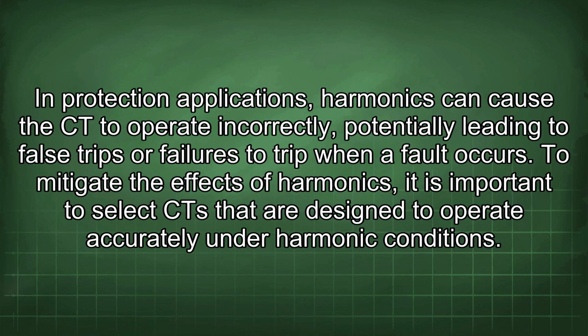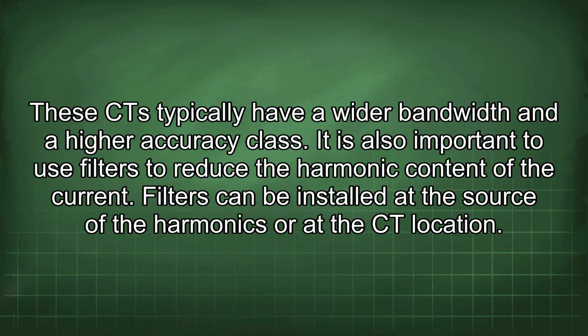In protection applications, harmonics can cause the CT to operate incorrectly, potentially leading to false trips or failures to trip when a fault occurs. To mitigate the effects of harmonics, it is important to select CT that are designed to operate accurately under harmonic conditions. These CT typically have a wider bandwidth and a higher accuracy class. It is also important to use filters to reduce the harmonic content of the current. Filters can be installed at the source of the harmonics or at the CT location.